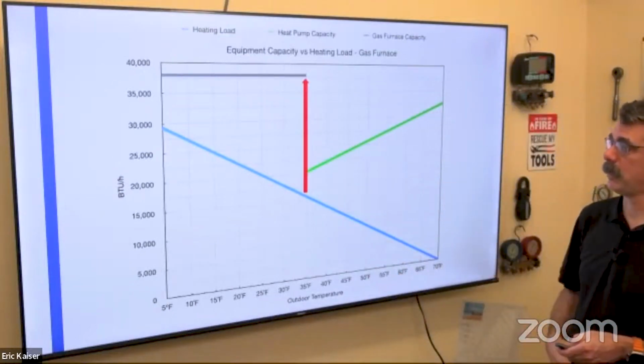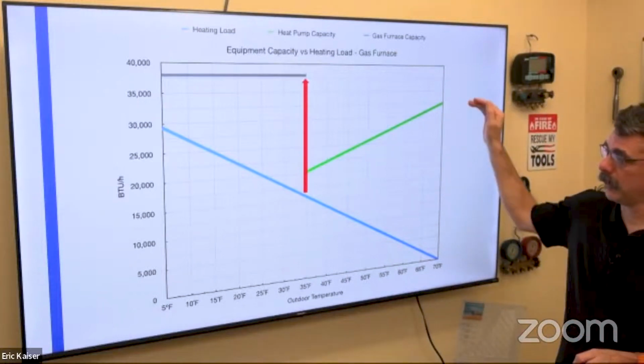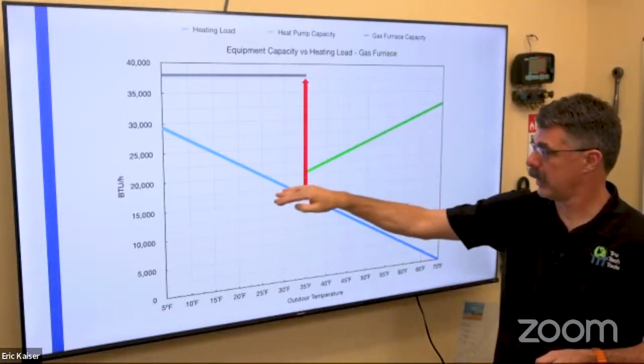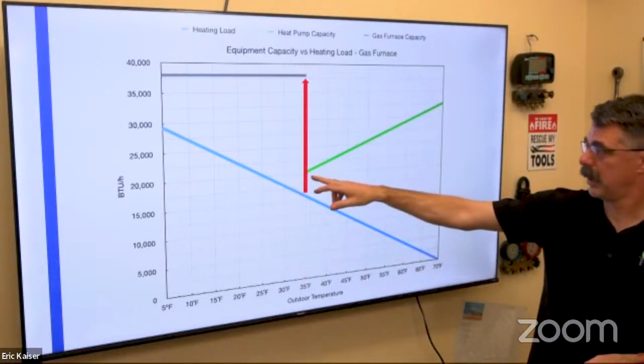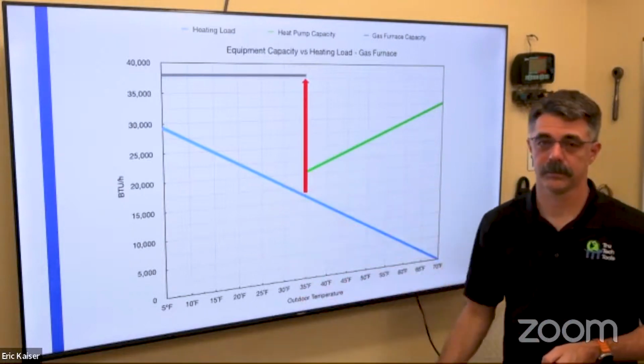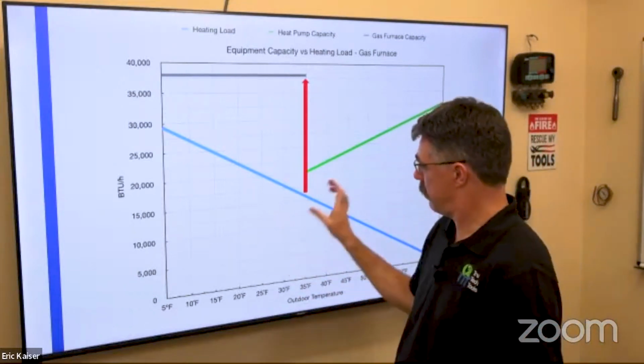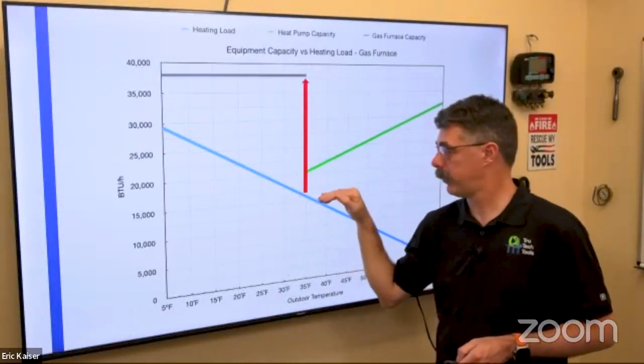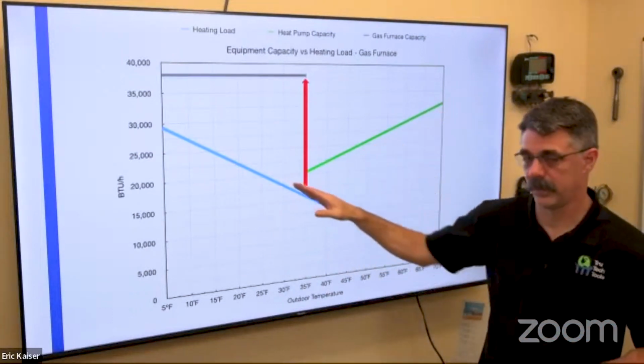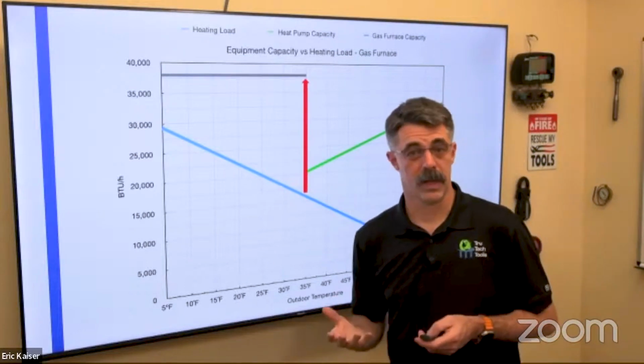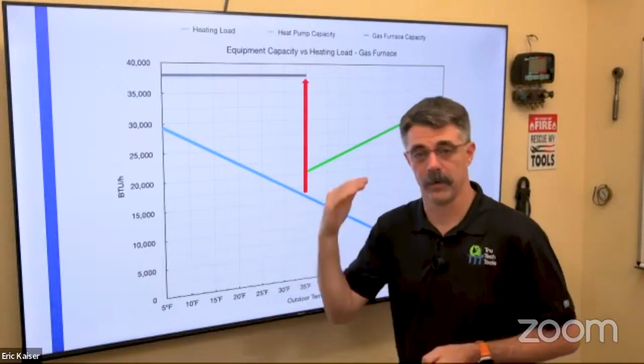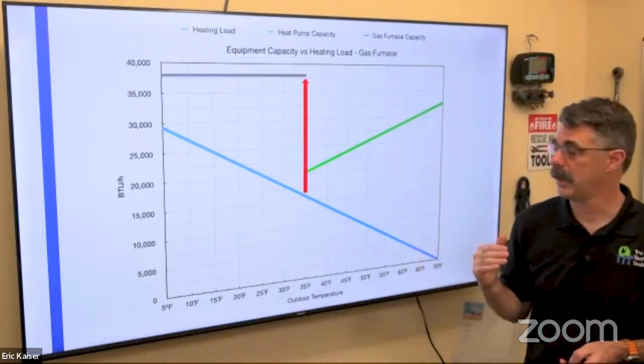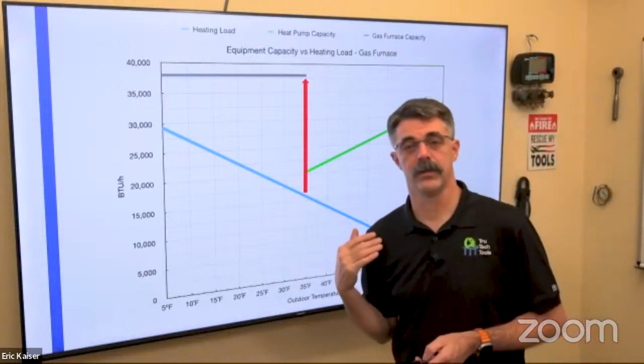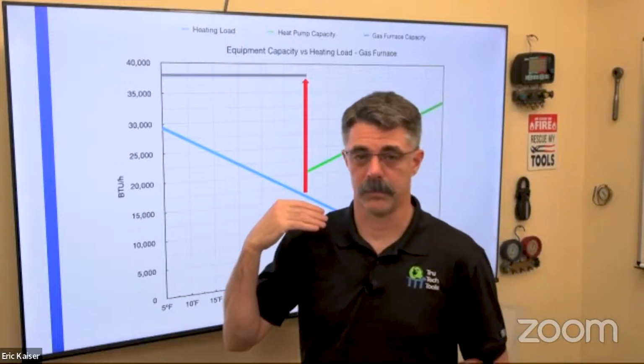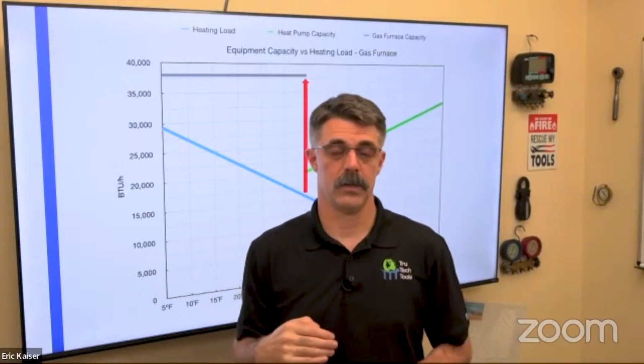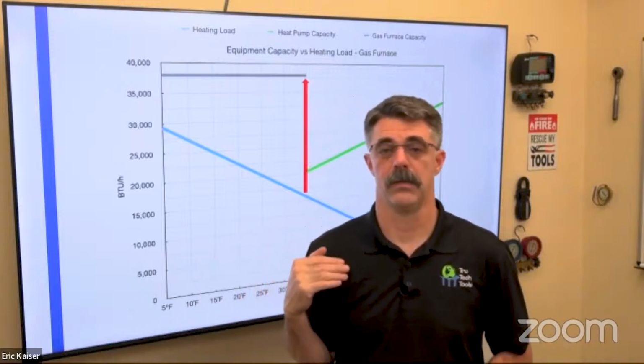Now, this is a dual fuel system. Okay, with a dual fuel system, we want to understand where that really crosses. And I could probably run it right down here to about 30 degrees. But one of the challenges here is this range right here, this 5 degrees before the heat pump performance line crosses the house load line. It can run a lot, which is really, really comfortable. There's no cycling off and on basically of the equipment. The house is really, really comfortable then, because the heat pump is providing almost continuous heat to that house where the house is losing continuous heat.